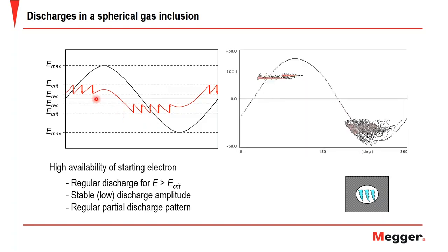And here you can see the phase resolved partial discharge pattern, or the PRPD pattern, that shows a regular partial discharge pattern for this stable low discharge amplitude. You can see a lower amplitude due to this charge and discharge from the critical field to the residual field. And it is uncommon to have such high availability of the initial electron as well as the stable magnitude, and this really only applies whenever there's strong radiation by X-ray or UV light that provides sufficient energy to achieve such regular discharge.